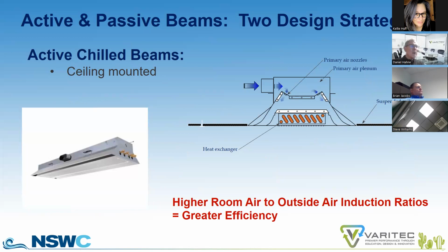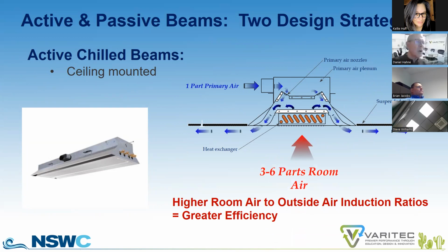So here's just a dynamic graphic to demonstrate how an active chill beam actually works. You can see how that high velocity airflow injected on opposite sides of the coil creates a negative pressure zone above the coil, drawing room air across the coil, where it mixes again with the outside air and is supplied to the space. An active chill beam system does create a mixed air condition within the space. It is not a thermally stratified environment. Air is injected at high velocity to create thorough mixing in the room. So consequently, you're going to hopefully achieve that plus or minus 2 degree temperature uniformity throughout the actual room.